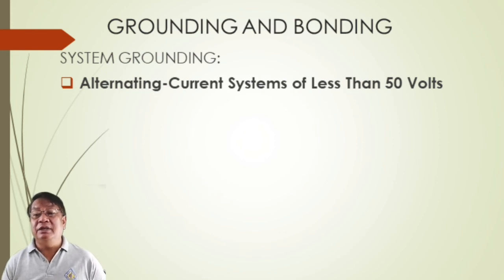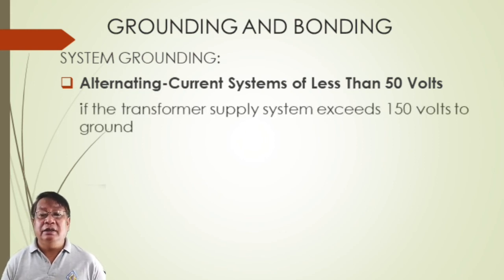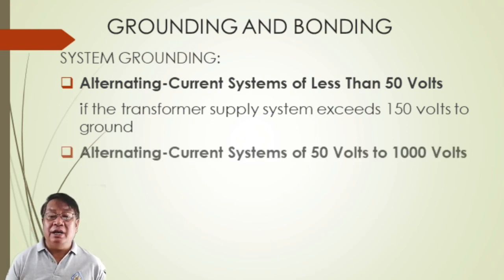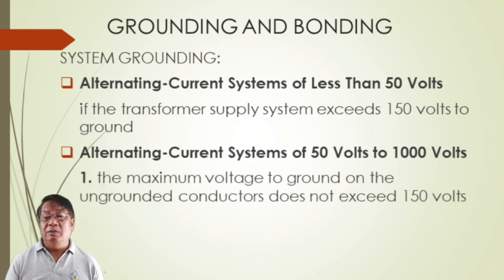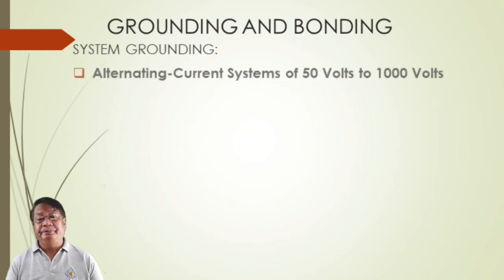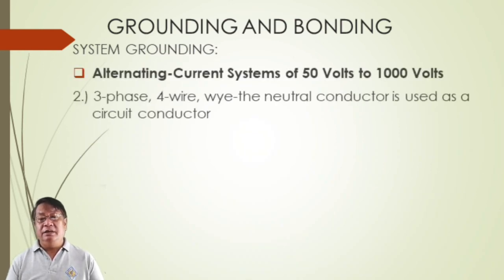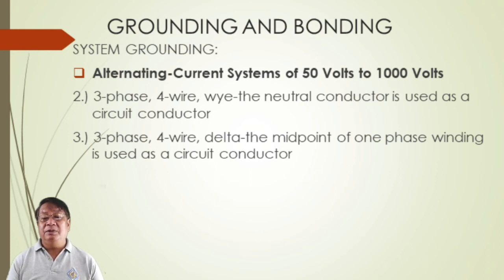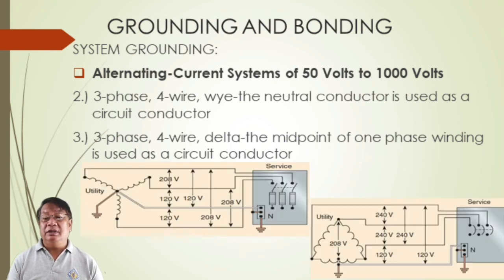For alternating current systems of less than 50 volts, if the transformer supply exceeds 150 volts to ground. For AC systems from 50 to 1,000 volts, the maximum voltage to ground from the ungrounded conductor shall not exceed 150 volts. For three-phase four-wire systems where the neutral conductor is used as a circuit conductor, or three-phase four-wire delta where the midpoint of one phase winding is used as a circuit conductor, grounding is required.